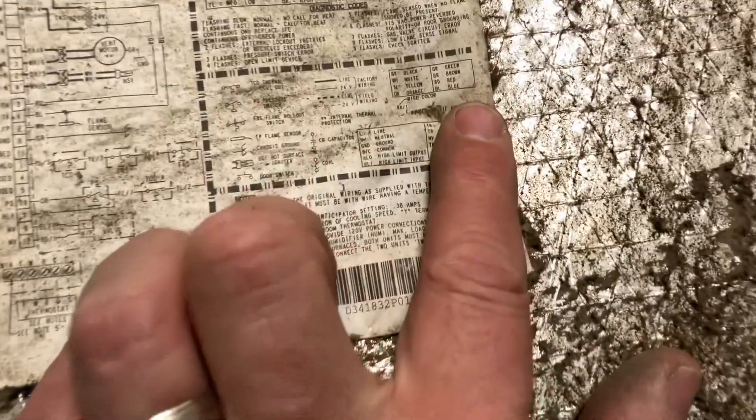It's not really running — the blower is running, that's about it. Let's see if there's an error code. It's a good system and it has an error code flashing four times. Let's open up the cover. The error code chart indicates: four flashes means high limit device.